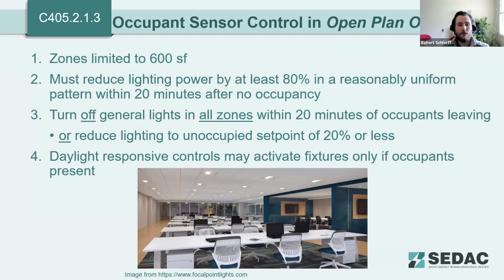So if your design, or if for some reason you decide that turning all the lights off is unsafe or unadvisable, you do have the option to reduce lighting power to a minimum set point of 20% to make sure that there's some safe passage lighting within those spaces. And then lastly, daylight responsive controls may activate fixtures only if occupants are present.